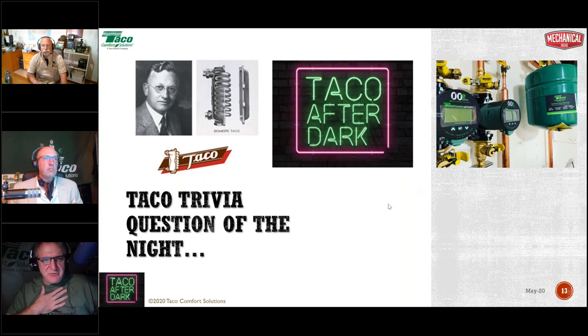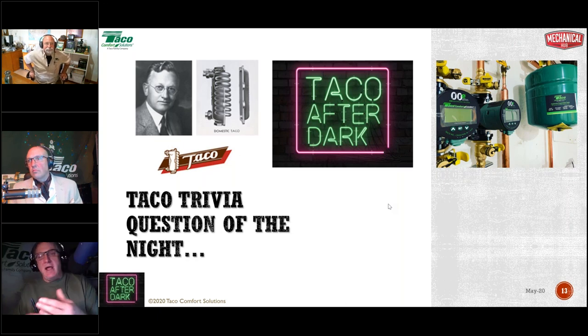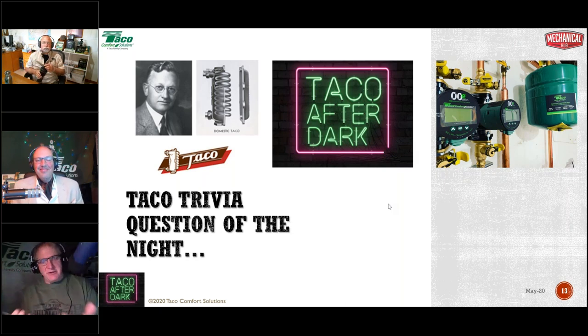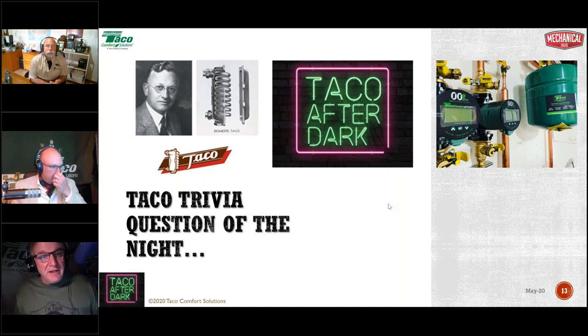Here's one. You assume these initial flows and heads; you don't understand that your calcs would be that far off. Well, Jim, that's a very good point. However, we're presuming the math has been done here. Here's the thing about heat loss calculations, whether it's the holy and sacred Manual J or IBR or anything else, they're all based on certain assumptions, and there are different percentages of fudge built in. None of them is dead-on accurate. They're all going to be very, very conservative, some more conservative than others. But to say I did a Manual J heat loss and that's the heat load is a little optimistic. You could be anywhere from 10 to 15% off, maybe 20% off.